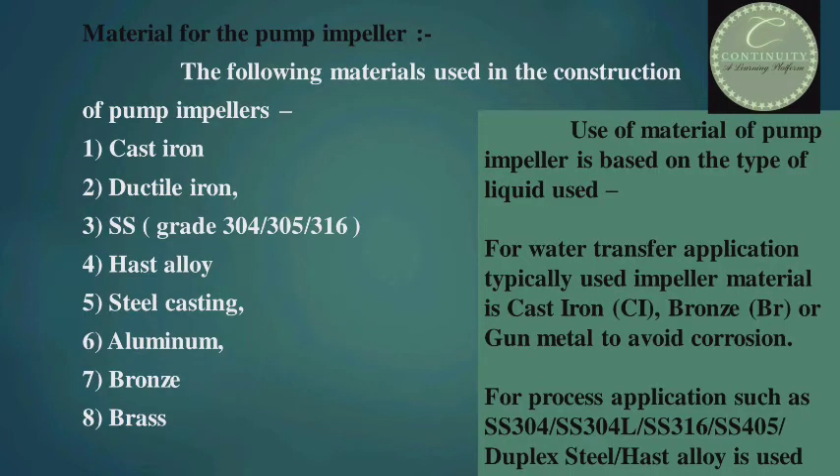Now I shall discuss the material of the impeller, i.e. of which material the impeller is made. The following materials are used in the construction of pump impellers: cast iron, ductile iron, stainless steel grades 304, 305, and 316, Hast alloy, steel casting, aluminum, bronze, and brass. The choice of material is based on the type of liquid used. For water transfer applications, typically used impeller materials are cast iron, bronze, or gun metal, to avoid corrosion.